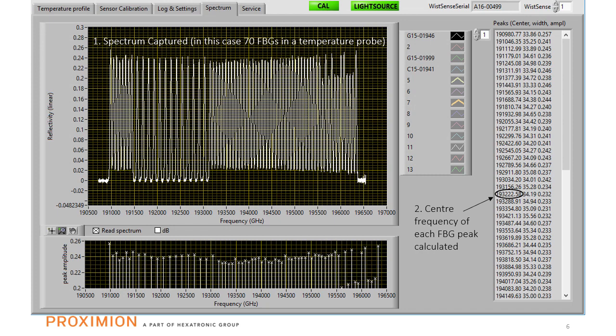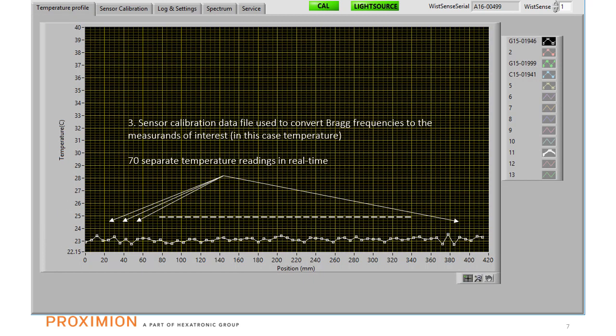Here is a typical display from Proximion's temperature monitoring software. The main display shows the spectrum from one fiber containing 70 FBGs. The lower display shows the amplitude of the FBG peaks. The small peaks on the right are an optical barcode which contains the sensor serial number and calibration information. The right-hand display shows the frequency of each FBG reflection, from which the temperature at each FBG location can be derived. The calibration table for the FBG array is used to convert each FBG wavelength into temperature. The result is a temperature profile along the length of the temperature probe as shown on this tab of the software.